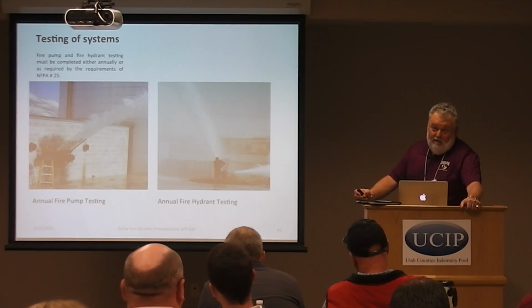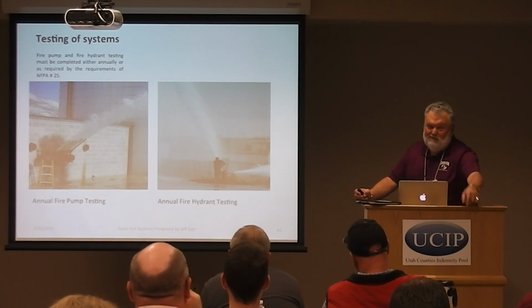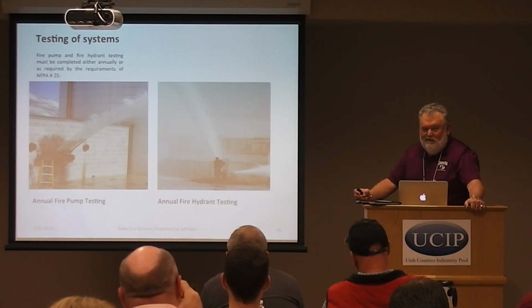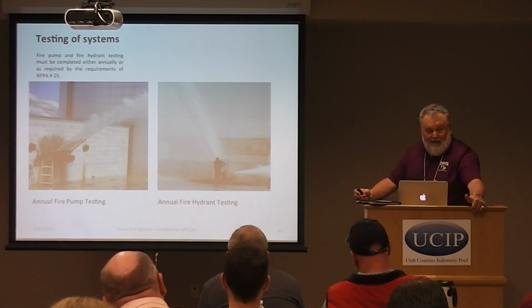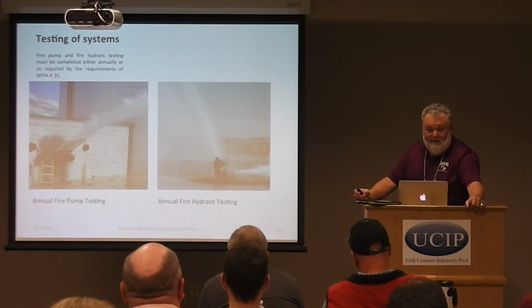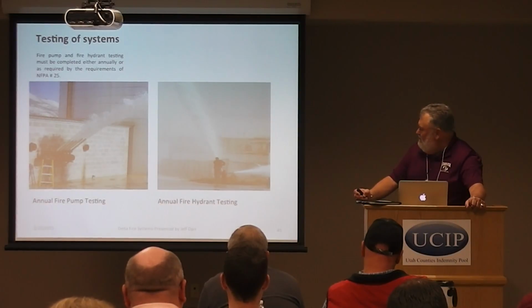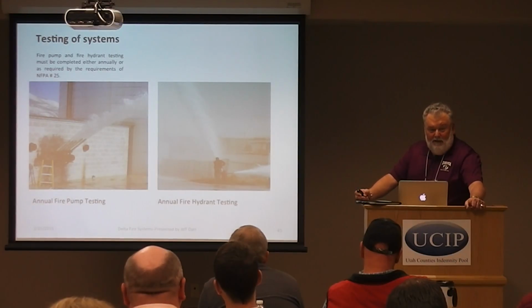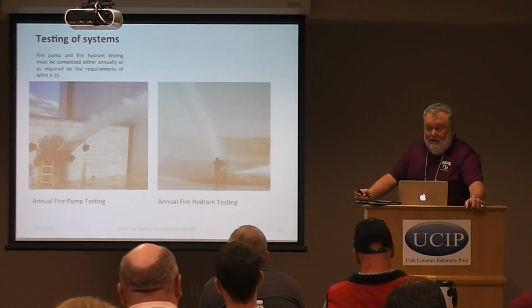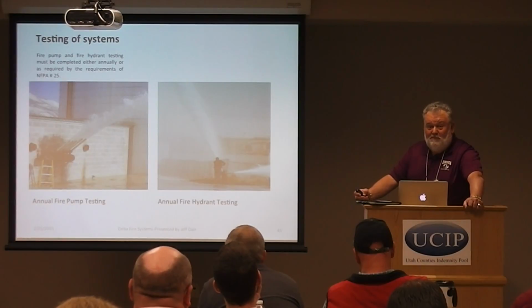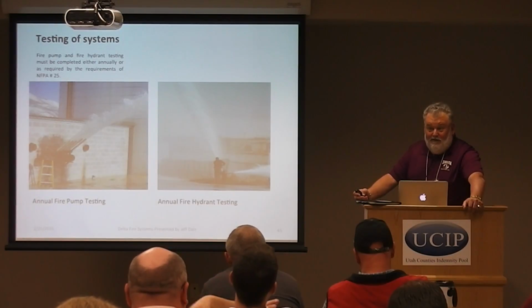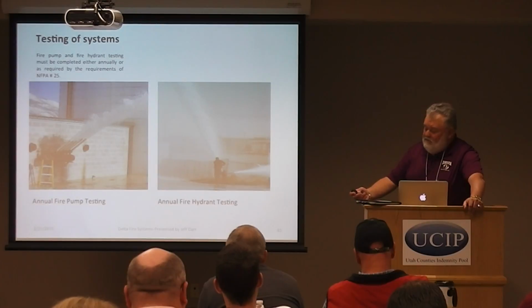You know, it's very rare that we do an inspection, and Kent's back here smiling, but he's always telling me, well, I can't get this thing to work right. And we found some of the dangdest things in casings of pumps and valves. And again, with the hydrants on the right here, we test the hydrants, make sure they work. We did one power plant here in Utah, and we found over 15 fire hydrants were not in operation. Kind of a scary thought for me, knowing that they go to the expense of putting these things in, and then they wouldn't even be able to use them.